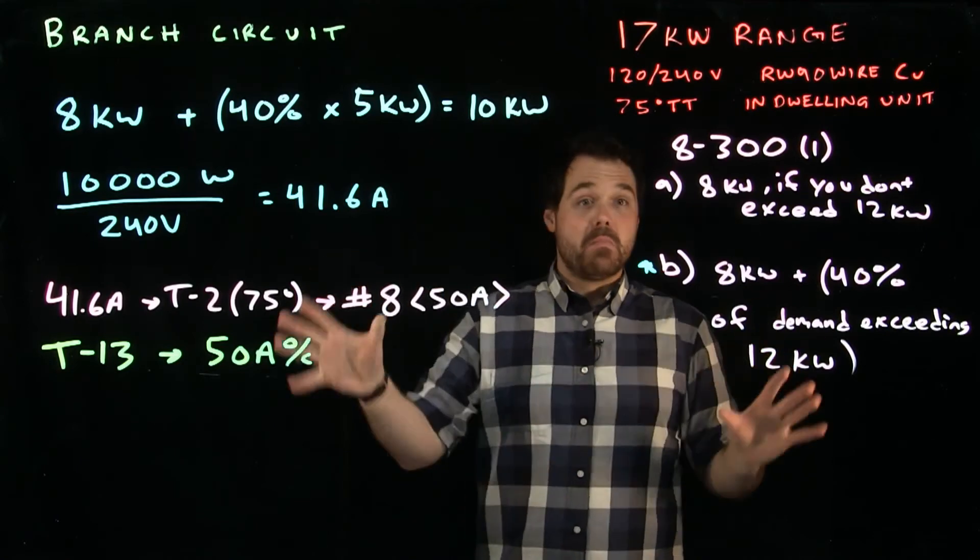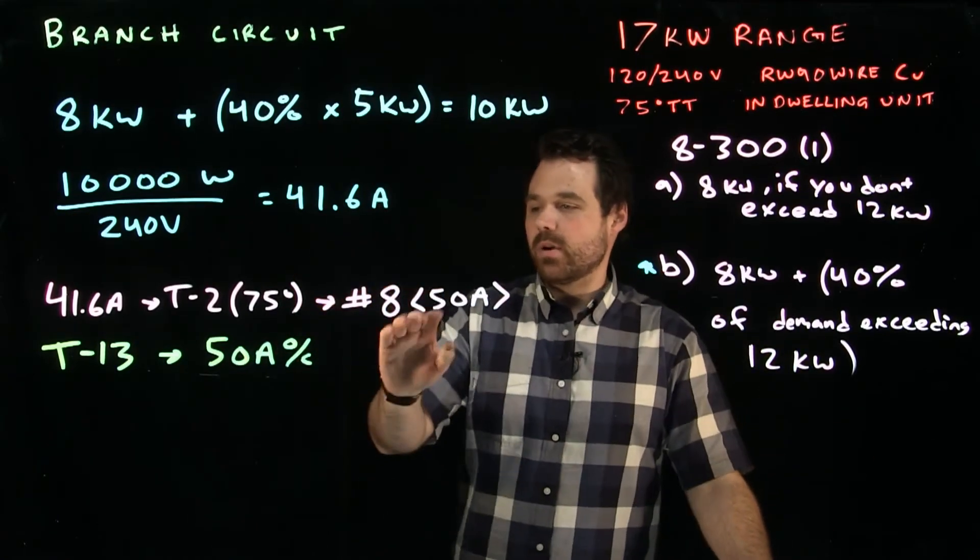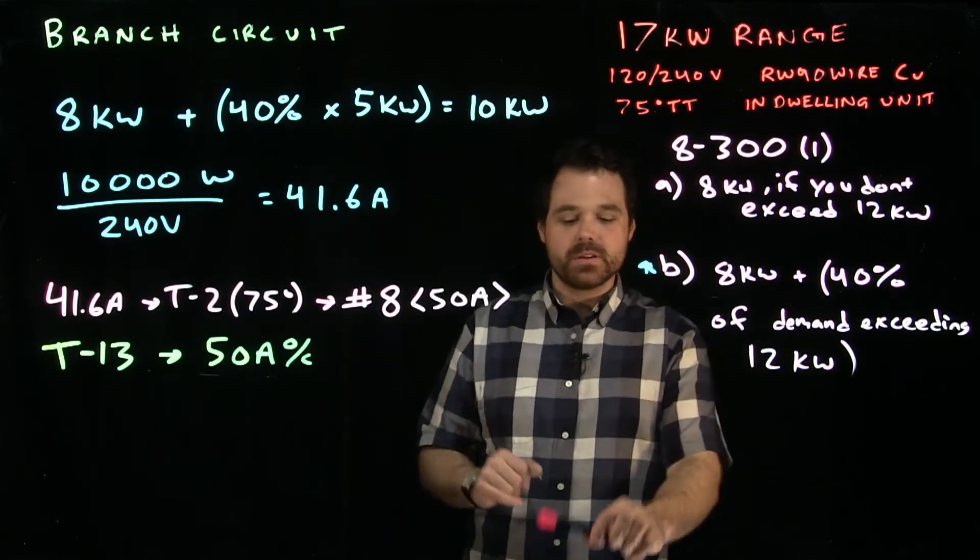Table 13 is going to tell us we would use a 50 amp overcurrent device on that number 8. Perfect. Fantastic. So that's basically the process to size a range. So we have our number 8. We got our 50 amp overcurrent. That's what we want to do.